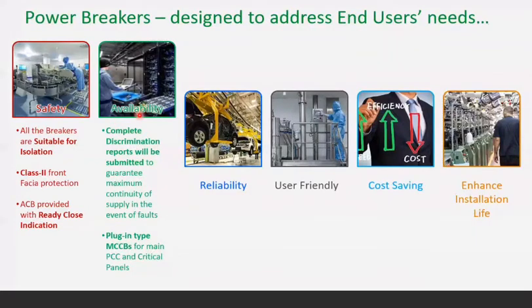Then in MCCBs, we have plug-in type MCCBs for main critical or PCC panels where availability or continuity of supply is of utmost importance. Within a minimum period of time we can change over. If there is any fault or the MCCB has blown off, we can replace it by going for the plug-in type.